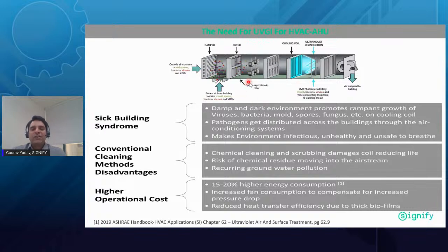The HVAC system's function is to provide clean air into the indoor environment, and if biofilm accumulates on the cooling coil, whatever air is coming inside will carry all those bacteria and viruses. That is why it will enhance sick building syndrome, because the people inside that building will get infected by those bacteria and viruses, and the cooling coil further contaminates the indoor air quality.